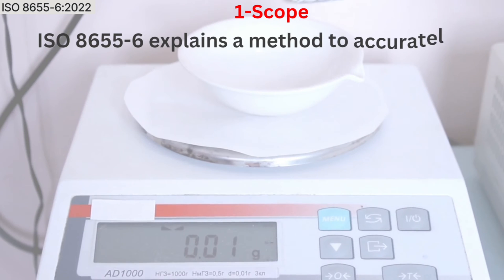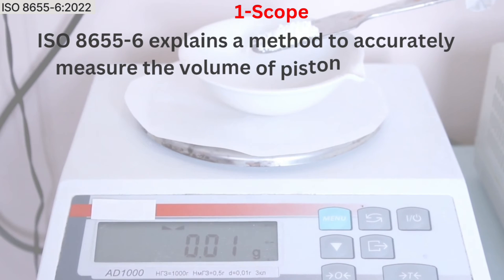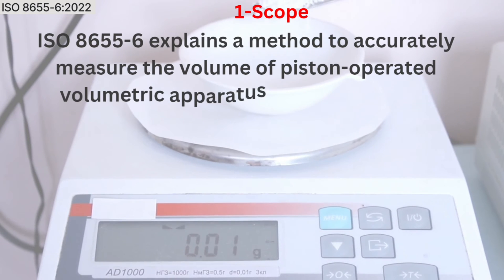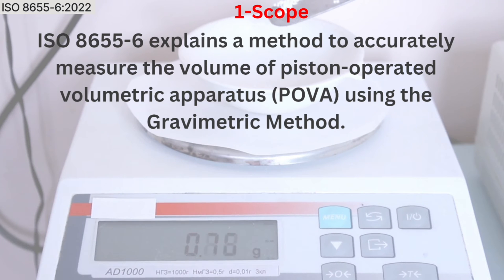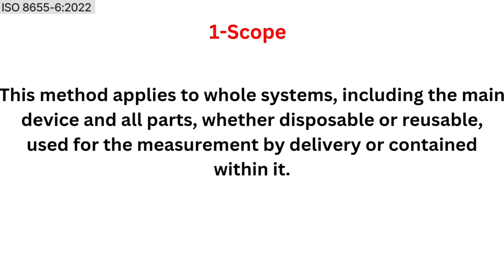Section 1, Scope: It explains a method to accurately measure the volume of piston-operated volumetric apparatus using the gravimetric method. This method applies to whole systems, including the main device and all parts, whether disposable or reusable, used for measurement by delivery or contained within it.